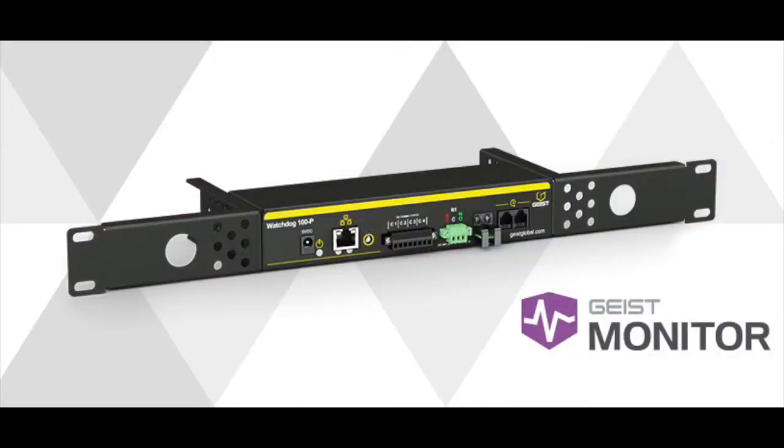So I've got the Watchdog 100. It's kind of like the Watchdog 15, but it has more access points. This is obviously rack mount, one unit device. So you can check your temperature and humidity, but you can also plug in dry contact points. This is great for leak detection. You can also plug in door opening alerts. And just like all of these products, SNMP alerts to your phone — so you can receive email or text message notifications, depending on how you configure it. All of the software is free to access. I think that kind of sums it up.